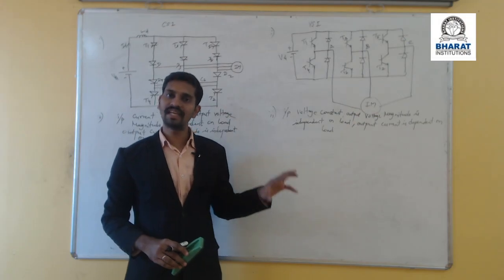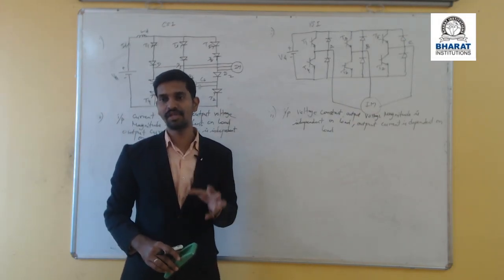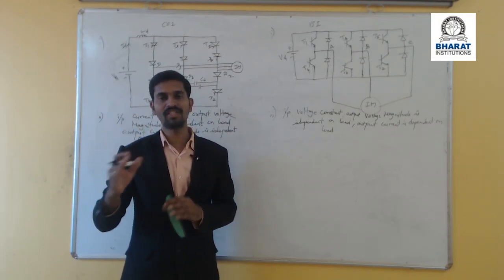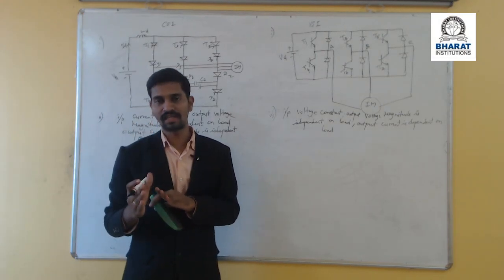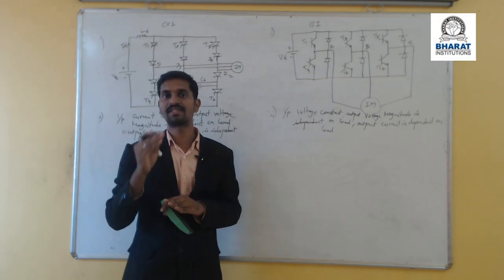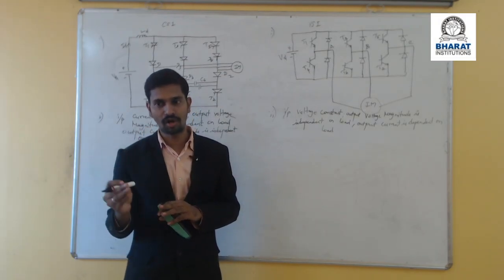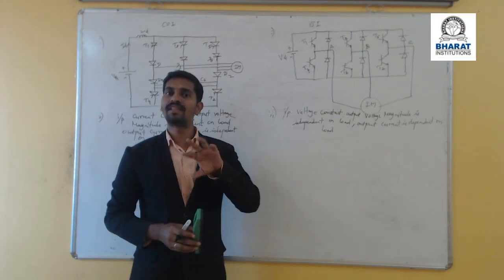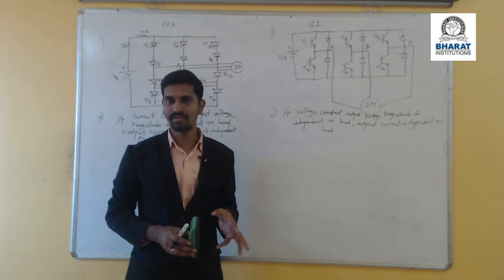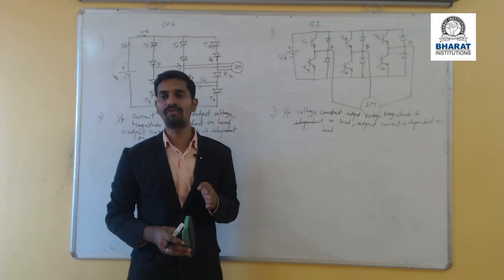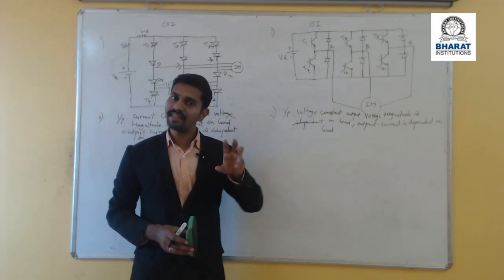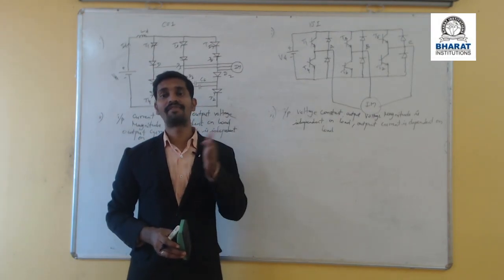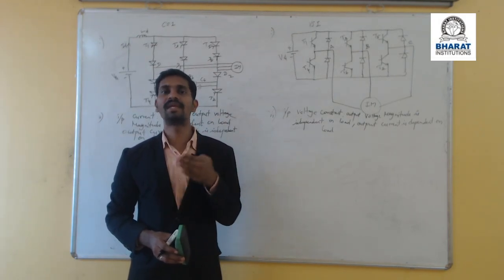The ultimate aim of VSI, CSI, and cycloconverter-fed induction motor is to achieve variable frequency, variable stator voltage, and to maintain the V/F ratio as a constant. To achieve this, we use VSI, CSI, and cycloconverters. By varying the firing angle of these inverters or cycloconverters, the reference frequency of the induction motor will be varied.